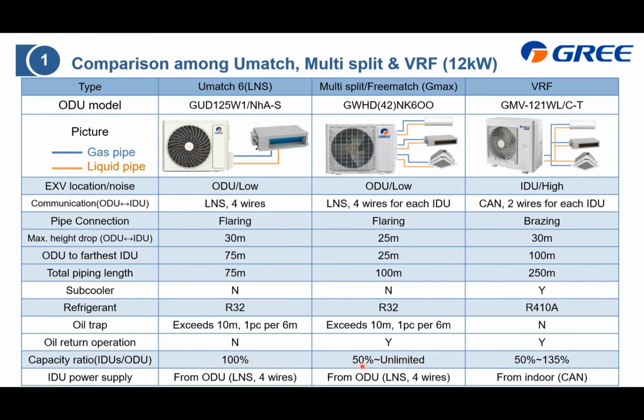And also the capacity ratio, for this one, there is no selection. And for this, it is 50 to 150, actually our recommendation is 150. It will lower the system performance, but generally there is no limit, but the quantity is already fixed by the outdoor unit. As for the VRF, we have a limit, upper limit is 135. And the power supply for this U-match is from outdoor unit to the indoor unit, and also the same as the multi-split. For the VRF, the power supply for indoor unit and outdoor unit are separated. Communication is CAN, only 2 wires.